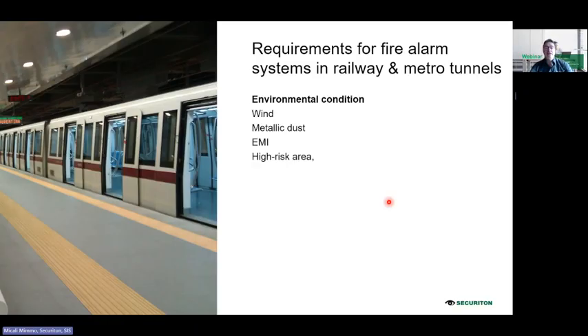Then it's also considered a high risk area if you have to access the inside of the tunnel, because of the trains with high speed coming in, and because we have power lines. So it's not very easy to access, and therefore if the system has the possibility of remote access and remote maintenance, that would be really preferred. Then, the same as in the road tunnel, we have different changes of temperature. Usually the tunnels in the railway sector are longer, so we may have a cold temperature at the beginning of the tunnel, and in the middle of the tunnel we may have 20 degrees of difference from the entrance. This kind of temperature must also be considered when you plan the fire detection system.